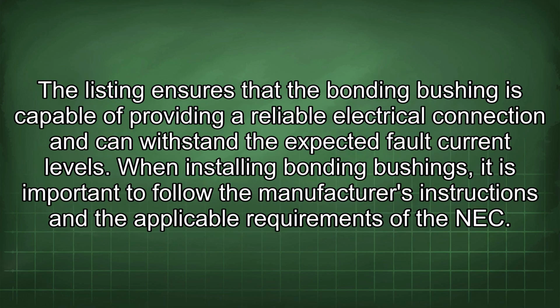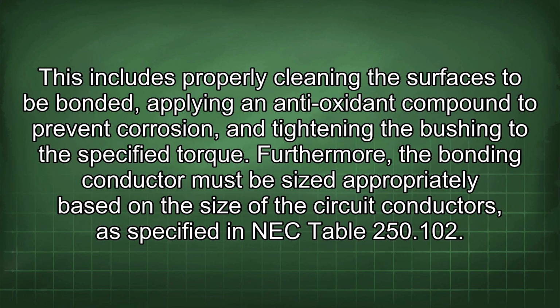The listing ensures that a bonding bushing is capable of providing a reliable electrical connection and can withstand the expected fault current levels. When installing bonding bushings, it is important to follow the manufacturer's instructions and the applicable requirements of the NEC. This includes properly cleaning the surfaces to be bonded, applying an antioxidant compound to prevent corrosion, and tightening the bushing to the specified torque.